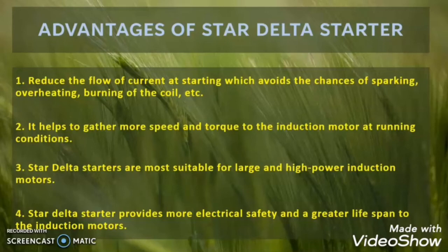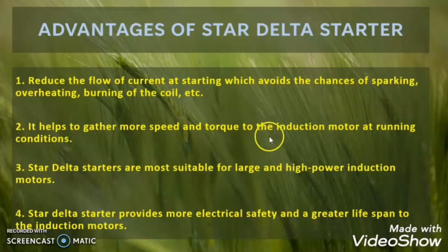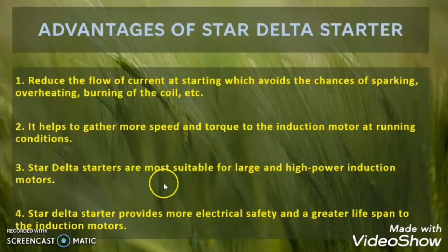Now let us understand the advantages and disadvantages of the star delta starter. First advantage: it reduces the flow of current at starting, which avoids the chances of sparking, overheating, burning of the coil, and insulation failure. Second advantage: it helps the induction motor gain more speed and torque during running time, since in delta configuration the motor receives the rated voltage, and speed and torque are directly proportional to the voltage applied. The star delta starter is most suitable for large and high power induction motors.